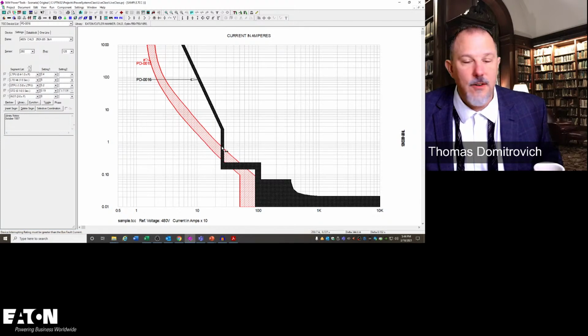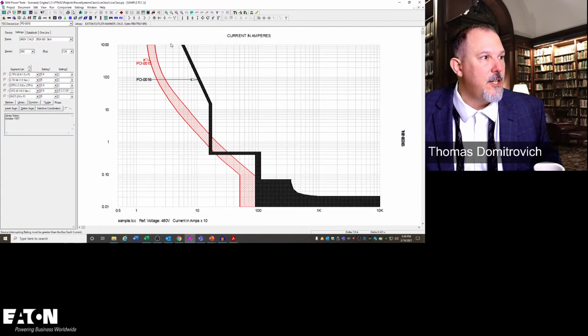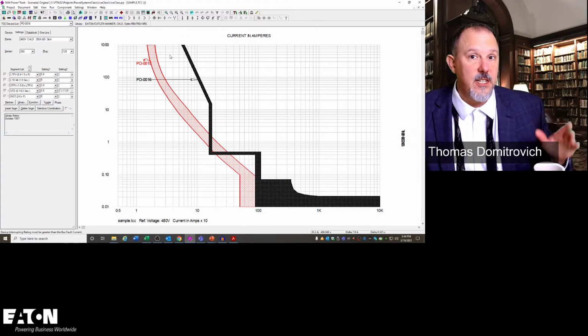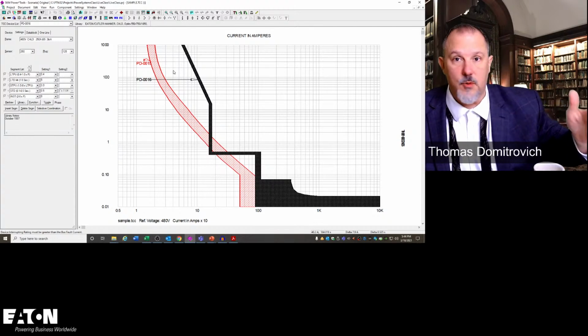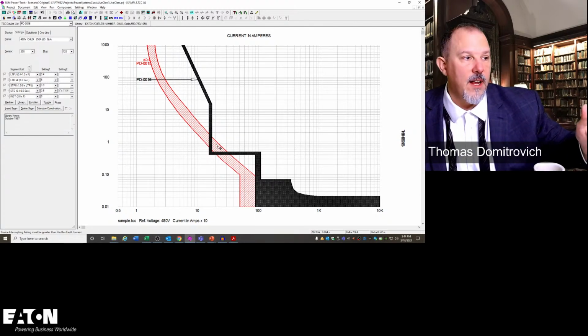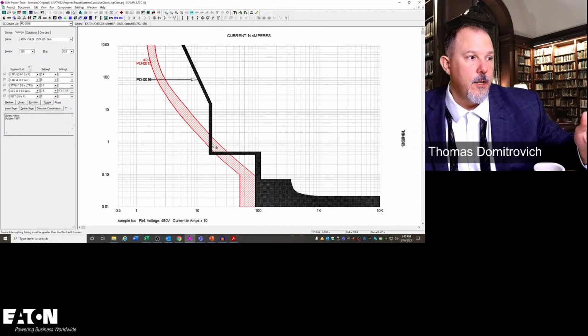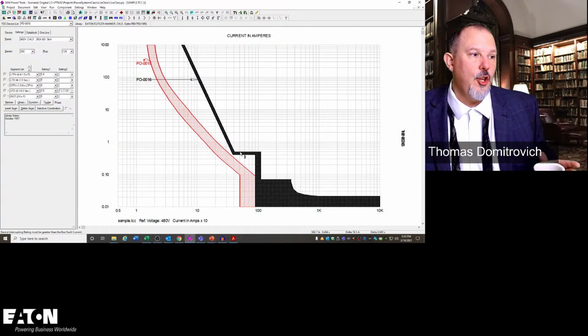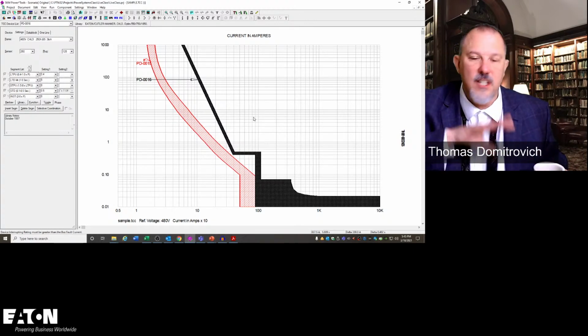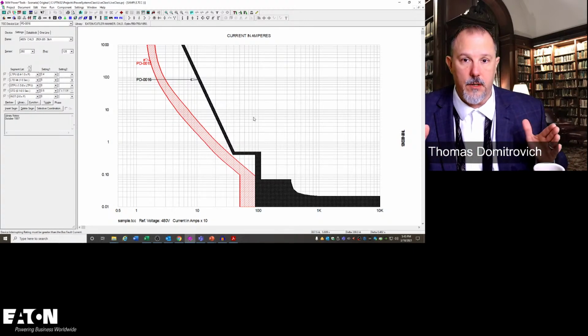So in this case here, I'm going to lower the short time pickup and raise the short time delay. I've adjusted this portion of the curve. I did not change instantaneous. I did not change the long time pickup. It is still protecting 125 amps worth of conductor. But what I've done is I've now destroyed my selective coordination for the fault currents in this region. So for that reason, you always have to plot these curves, especially in the world of circuit breakers.